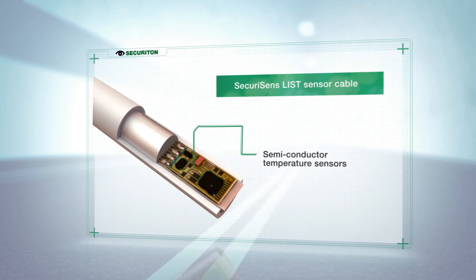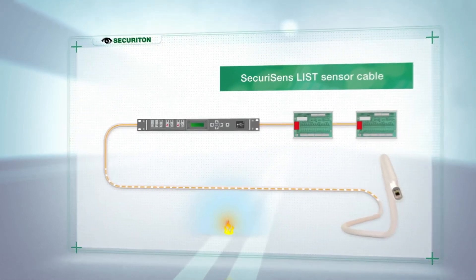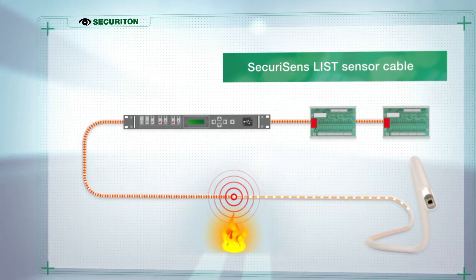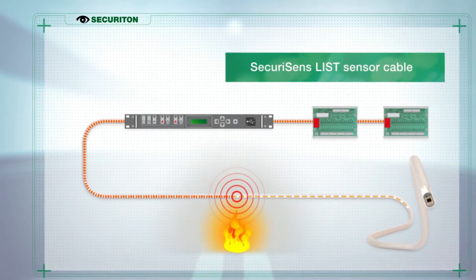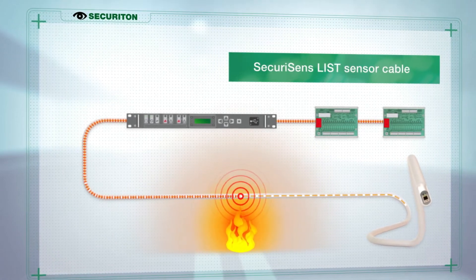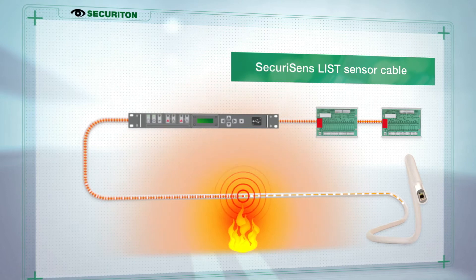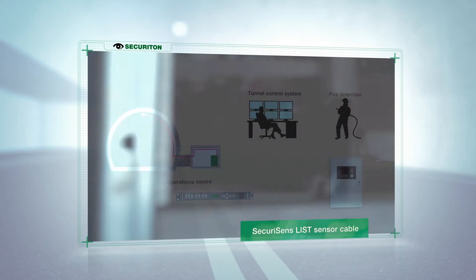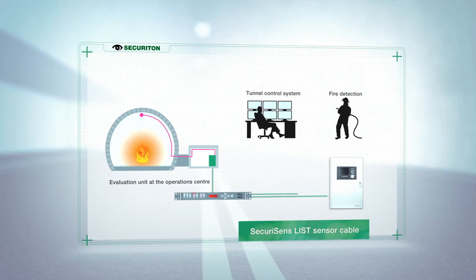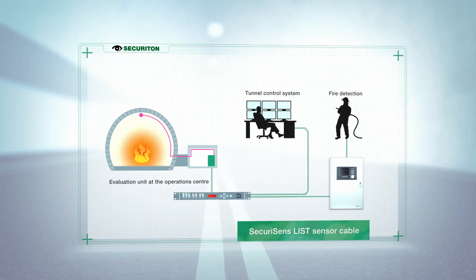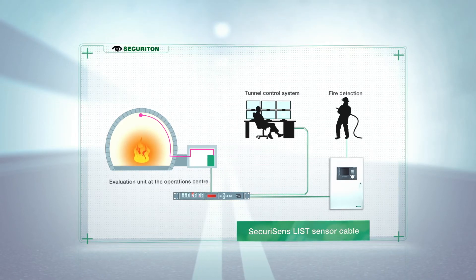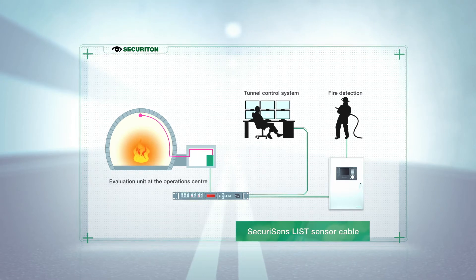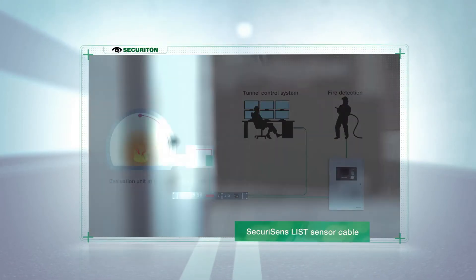The operating principle behind the SecuriSens LIST sensor cable is simple. Located inside the cable, semiconductor temperature sensors measure the ambient temperature and send this to the evaluation unit. Here, the temperatures are compared with the defined threshold values and an alarm is triggered if these values are exceeded. The evaluation unit is located in the operation center of the tunnel. From here, the alarm signals are passed on to the fire alarm control panel, and at the same time the temperature values are also forwarded to the tunnel control system. This allows for continuous temperature monitoring in the entire tunnel and the possibility of detecting temperature trends.